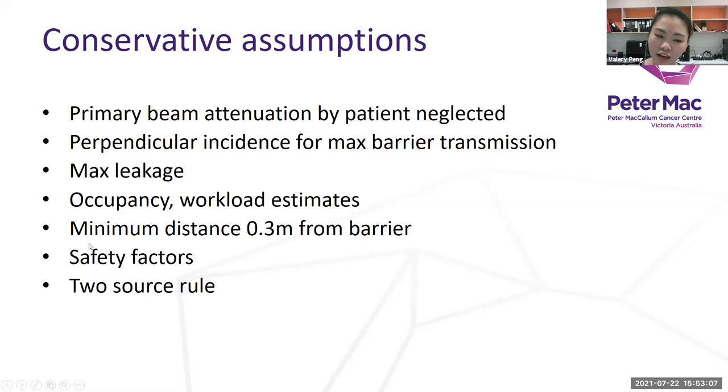And safety factors and also the two source rule. That's just adding, or choosing the larger thickness. And if the difference is less than one TVL, we add an HVL.